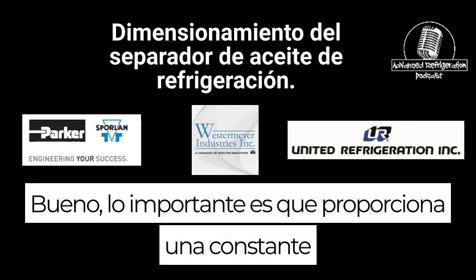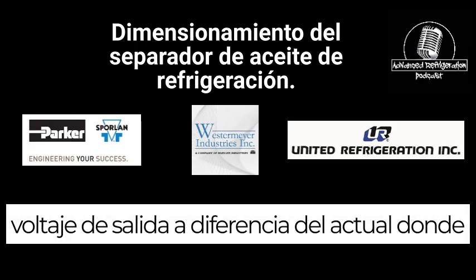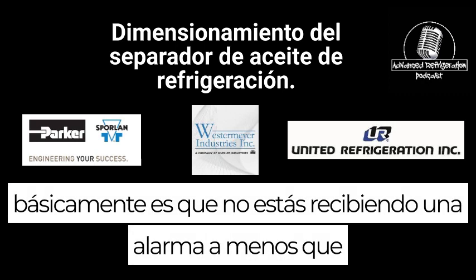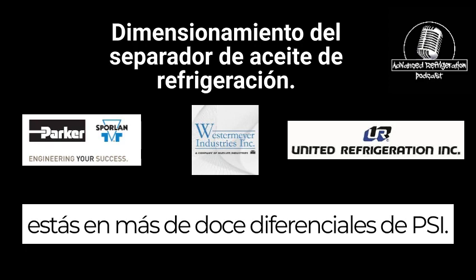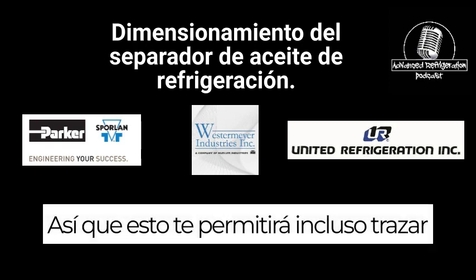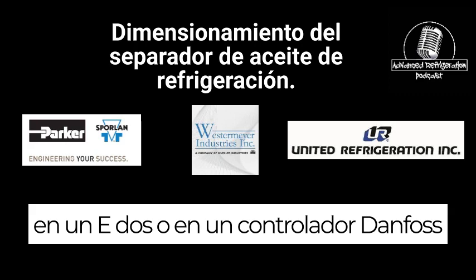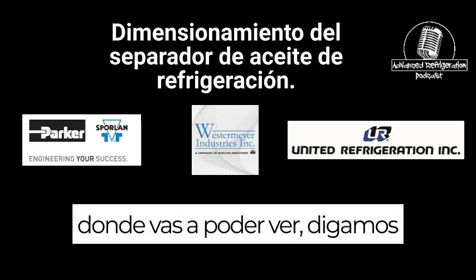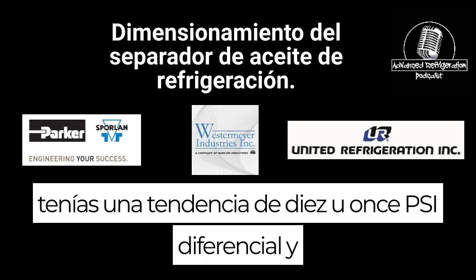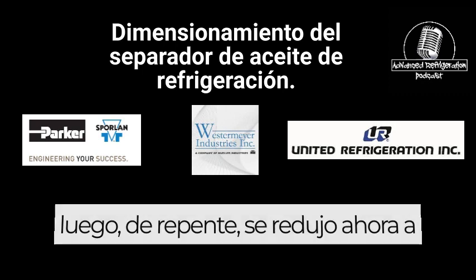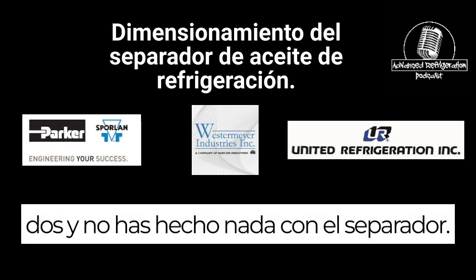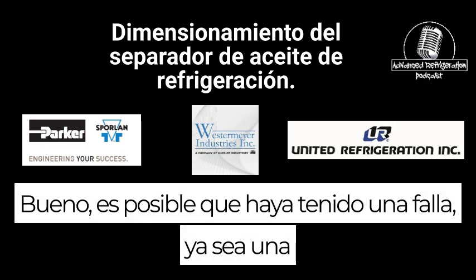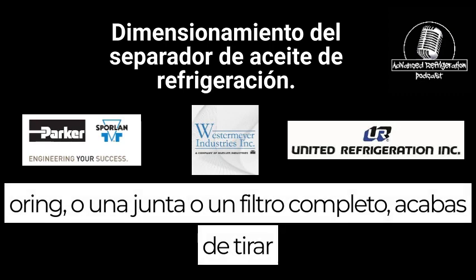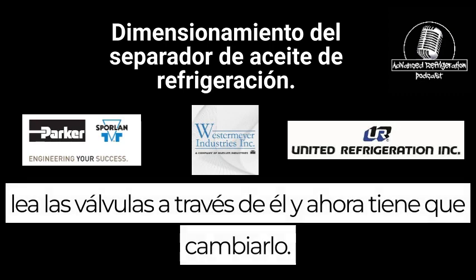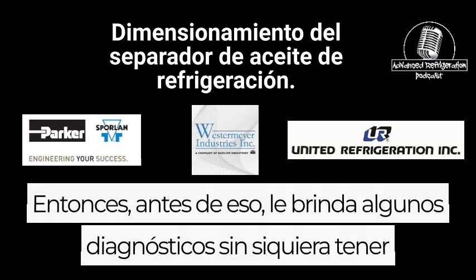Well, the big thing is it provides a constant output voltage as opposed to the current one, where basically you're not getting an alarm unless you're at over 12 psi differential. So this is going to allow you to even plot it out on an E2 or a Danfoss controller, where you're going to be able to see, let's say you were trending at 10 or 11 psi differential, and then all of a sudden it's dropped down to 2, and you haven't done anything with the separator. Well, you may have just had a failure, whether it's an O-ring or a gasket, or a complete filter you just threw reed valves through it, and now you got to change it. So that gives you some diagnostics without even having to open up the separator.